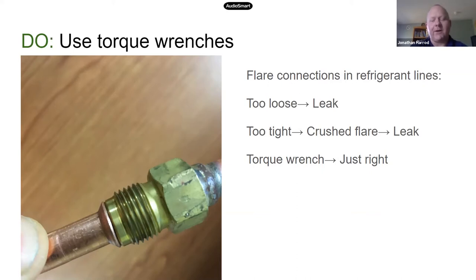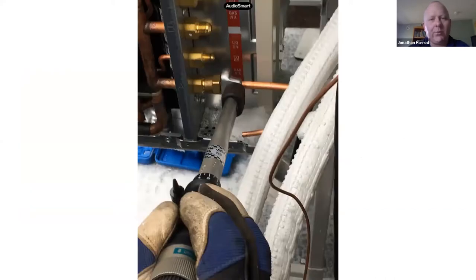If you can imagine the different level of force you'd need to lift a 13-pound dumbbell versus a 55-pound dumbbell, and then try to imagine doing that just based on feel, you'll understand quickly that it's not possible. Instead, we use these torque wrenches. You set them to the desired torque, and then you tighten the flare nut, and when you reach the desired torque, you hear a click and you stop. This is the way to know that we're getting the correct tightness on these flare nuts.